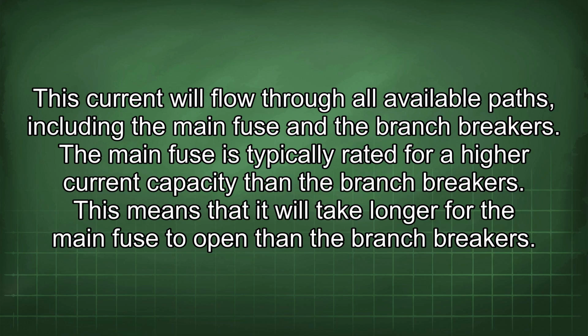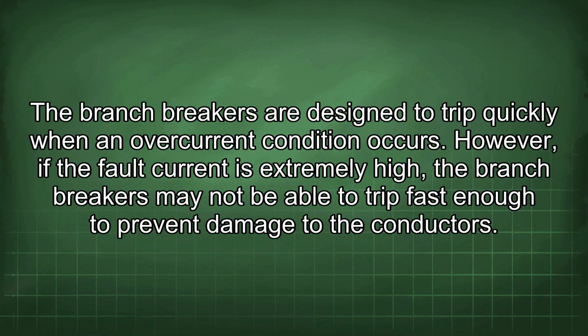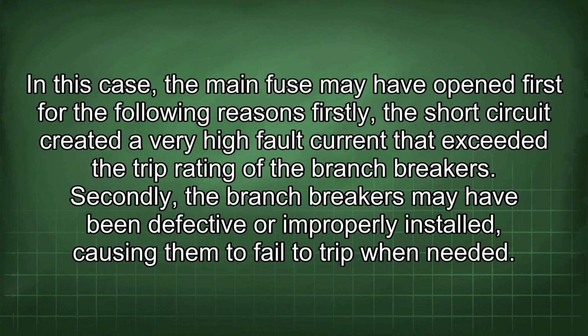The main fuse is typically rated for a higher current capacity than the branch breakers. This means that it will take longer for the main fuse to open than the branch breakers. The branch breakers are designed to trip quickly when an overcurrent condition occurs. However, if the fault current is extremely high, the branch breakers may not be able to trip fast enough to prevent damage to the conductors. In this case, the main fuse may have opened first for the following reasons.